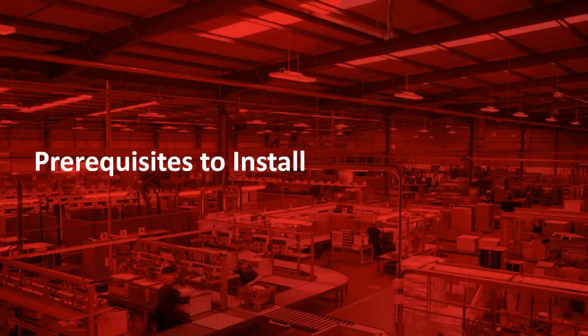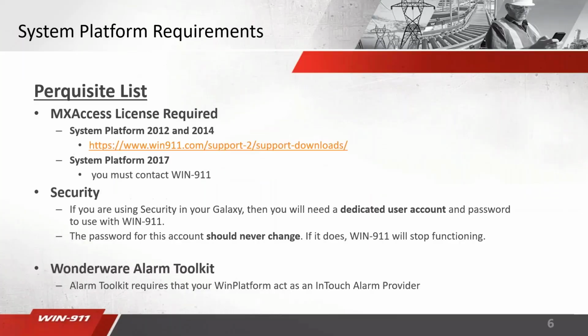Some prerequisites to be aware of for the installation. You need an MX Access license that's required. That is essentially what is responsible as the middleman for taking the acknowledgements that happen from WIN-911 and pushing them back into your System Platform setup. And you can get the MX Access license from our website for System Platform 2012 and 2014. You can just go to our website, go to the support tab, and to support downloads.